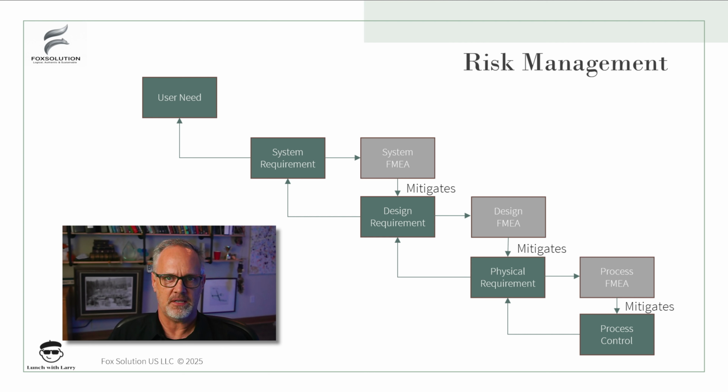And that puts us in a position where, when we get the post-market data back in, we can associate it with a line in the FMEA and have a very clear understanding of what our contract with the FDA is. You know, it's not a contract, but you understand what I'm saying. If I say it's 1 in 1,000, and I justify deployment of the device based on 1 in 1,000, and it comes in at 1 in 100, I have a problem.